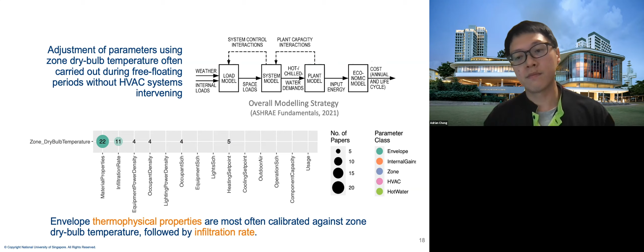This slide shows the steps taken in the calibration process. First, we built a model according to the as-built drawings as well as the specification without any measured data. Then we provided the measured exterior conditions as the boundary conditions. In level 1, we took the heat flux and RTD sensors to run measurements and try to derive the wall and window U values.